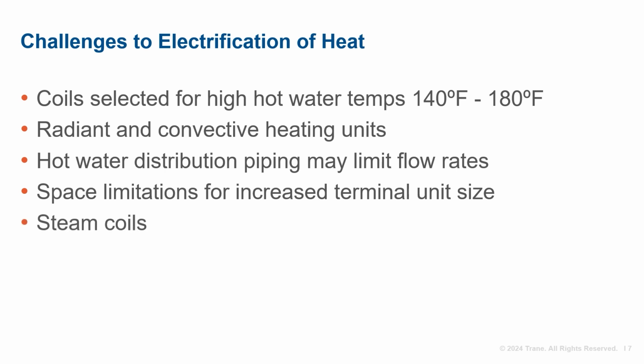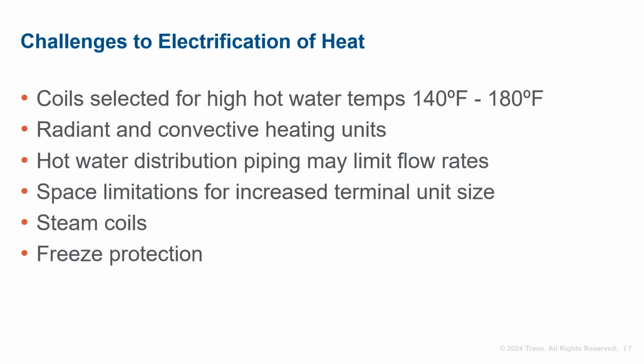Many existing buildings, particularly hospitals or large district or campus systems, still use steam heat that may need to be replaced. Steam is often used as a preheat coil since it's much less likely to freeze. When moving to hot water, the designer must consider freeze protection. And the last hurdle to electrifying heat, specifically in existing buildings, is cost. We'll discuss several options on how to address these issues.